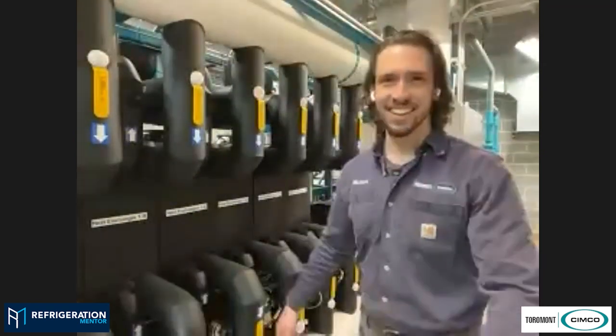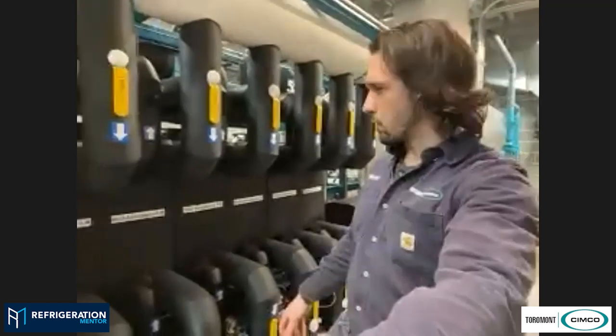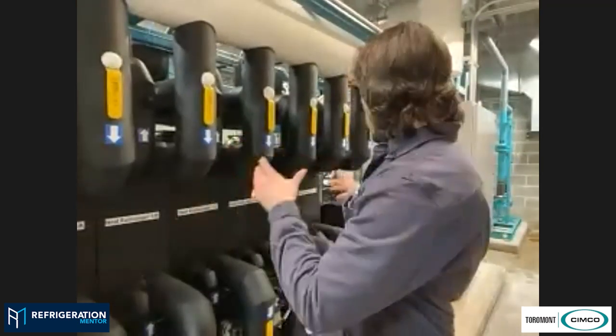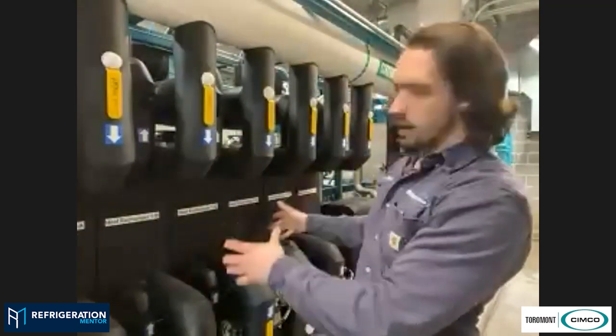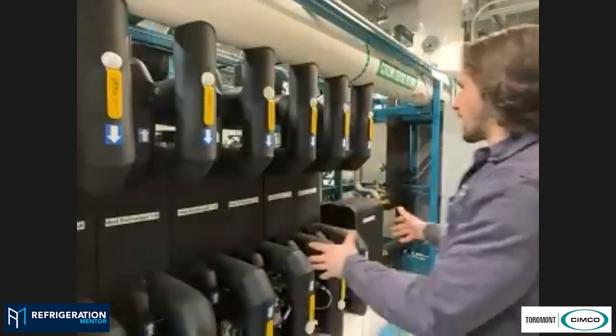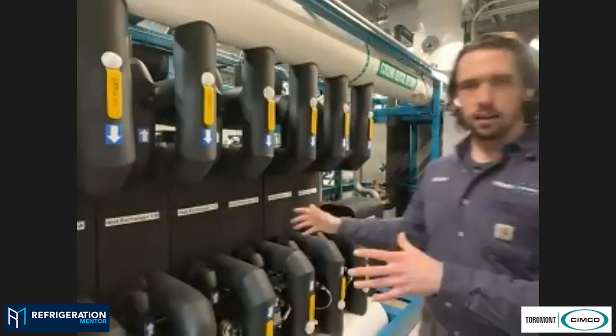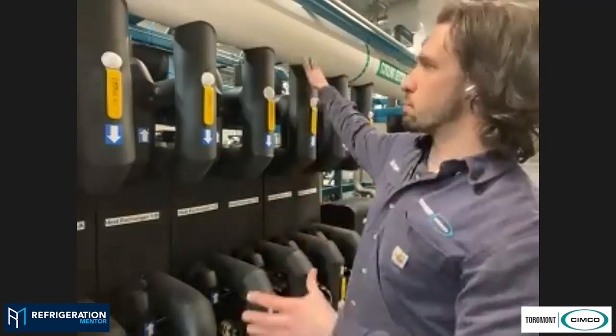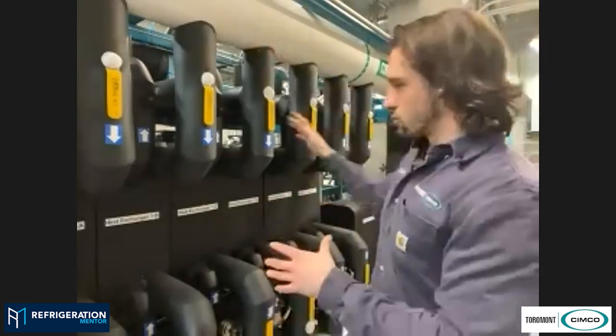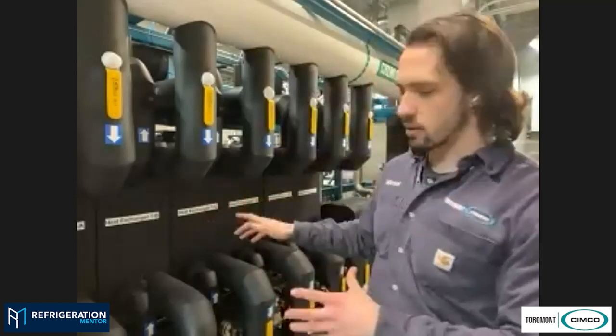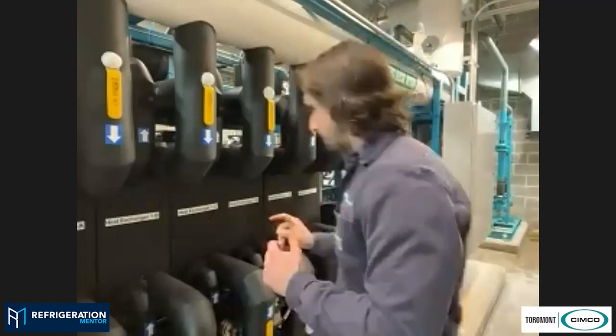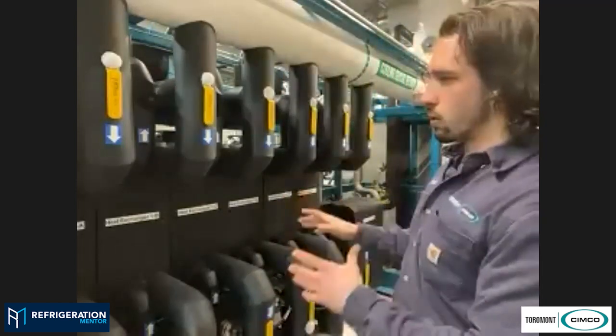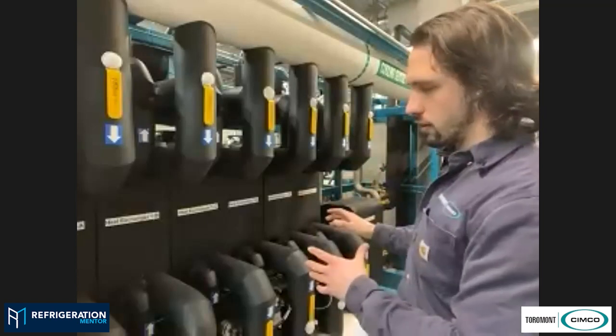So, over here these are our evaporators, our brazed plate heat exchangers. We have six of them in parallel with each other, and the glycol flow flows through all exchangers simultaneously, regardless of whether or not they're actually calling for cooling. The way we're controlling the amount of exchangers is based off glycol return temperatures.